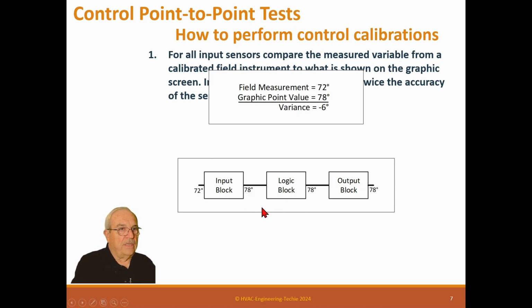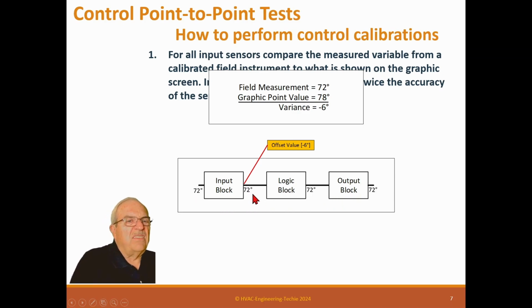Well, to do an offset, see, like this is the sensor coming in at 72 degrees, and then this goes 78 degrees through the device, so it outputs 78 degrees. So what we want to do is change this to match the 72. So we put an offset of minus 6 degrees, and we want it to go right there at the input block. Now, some systems actually let you do exactly what I've shown here. You have a little window you put there, and you put your value in here, which would be minus 6. And whenever that comes out of the system, it comes out at 72, because it's now got that minus 6 degrees.